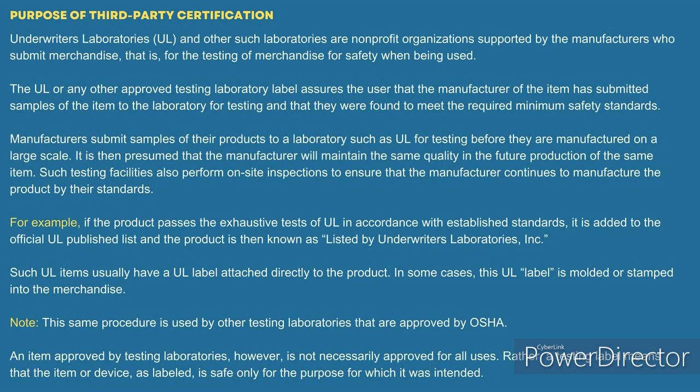Now, one big thing I want to throw out a huge disclaimer on. A lot of people, we might actually do this as a myth, and this could even be one we throw in there. Everyone thinks that every electrical part has to be UL listed. That's not true. They can be listed by different agencies, but they're listed under the same standard. That's right. So it's a UL standard, not necessarily UL. So that gets confused a lot. That's another myth that we might have to bring up, but I just wanted to throw that out there. Yeah, we can do that.